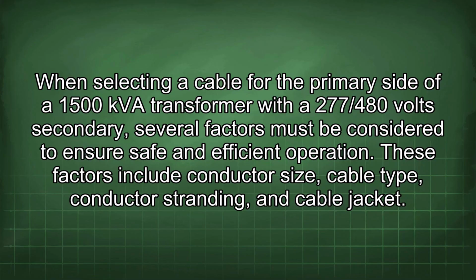When selecting a cable for the primary side of a 1500 kVA transformer with a 277/480 volt secondary, several factors must be considered to ensure safe and efficient operation. These factors include conductor size, cable type, conductor stranding, and cable jacket.